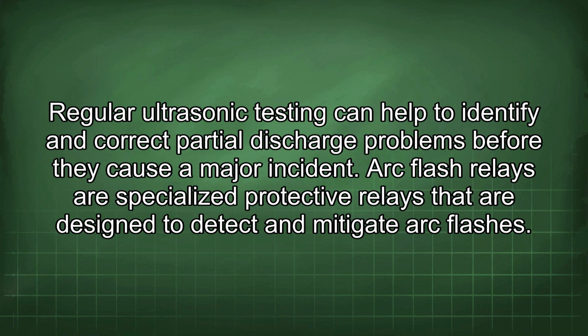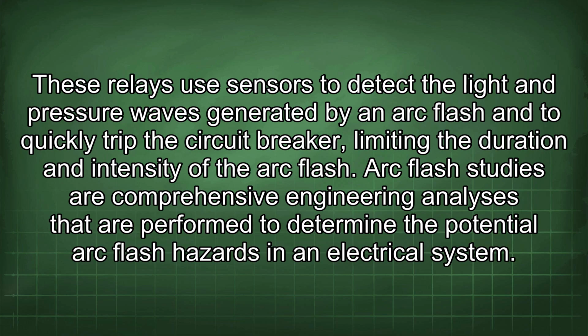Arc flash relays are specialized protective relays that are designed to detect and mitigate arc flashes. These relays use sensors to detect the light and pressure waves generated by an arc flash and to quickly trip the circuit breaker, limiting the duration and intensity of the arc flash.